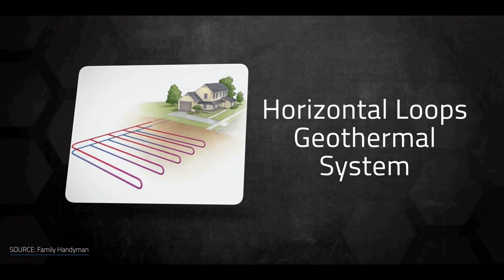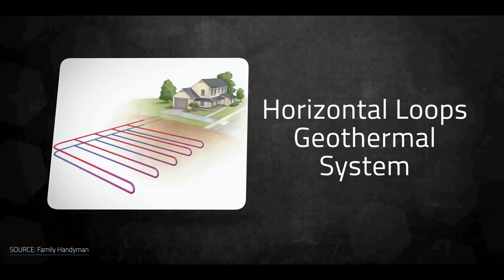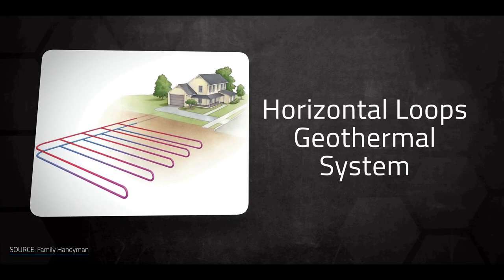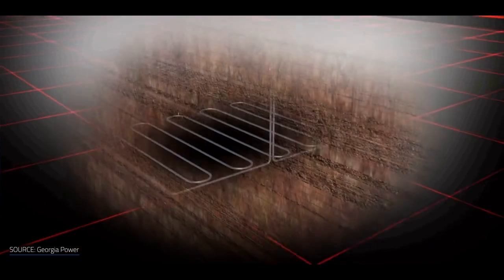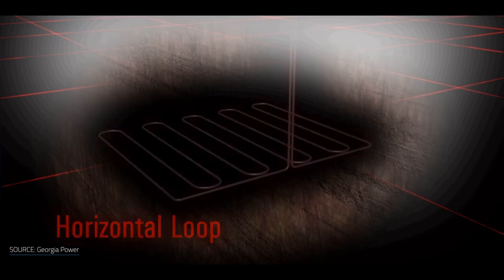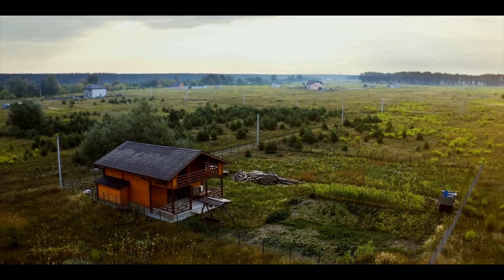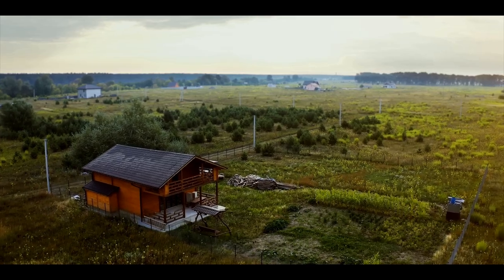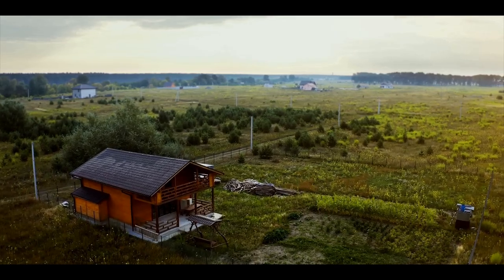Horizontal loops, just as the name implies here too, are composed of pipes that are placed horizontally in the soil, with the tubing being buried about 1 to 3 meters underground, but the length can be up to 120 meters. They take up a lot of room. If the loops are installed too shallow, they can run too cool in winter months. Horizontal loop systems are usually installed in locations with larger amounts of ground available for digging, such as farms, country houses. Like I said, you need a lot of space.